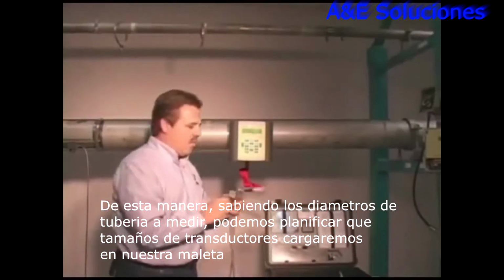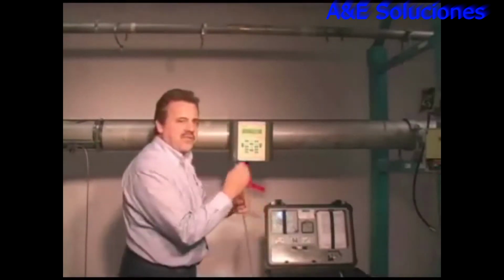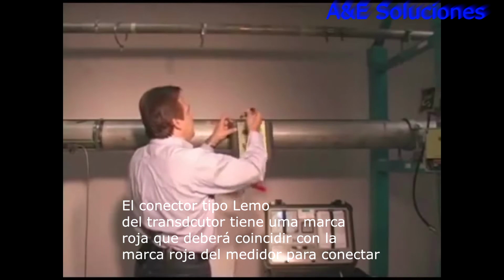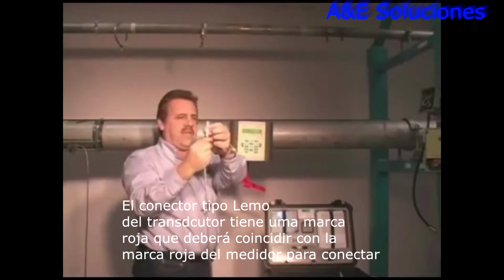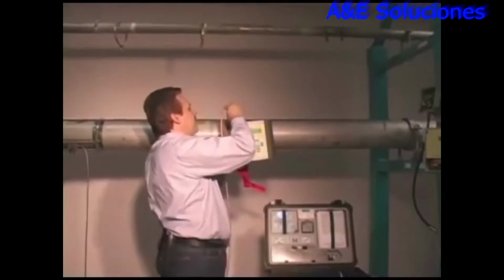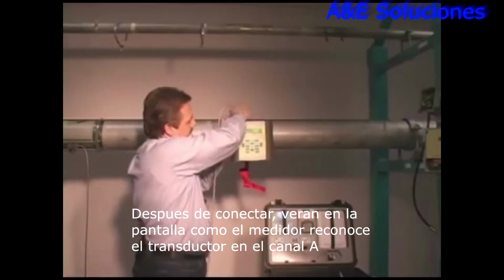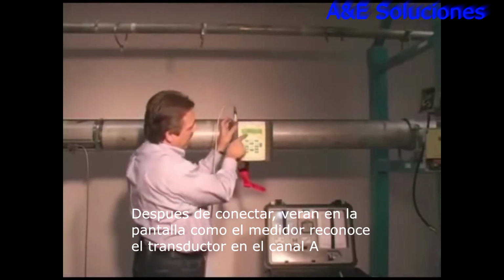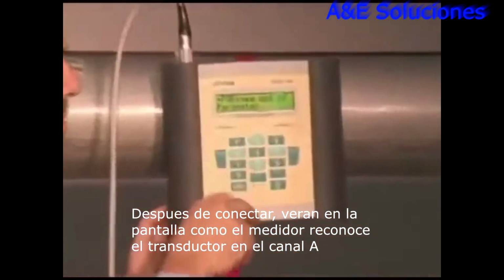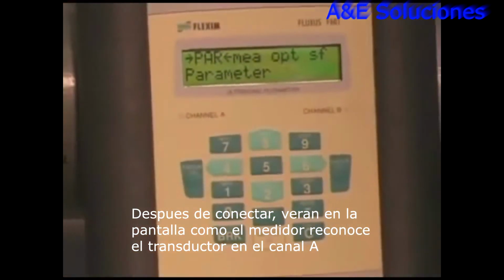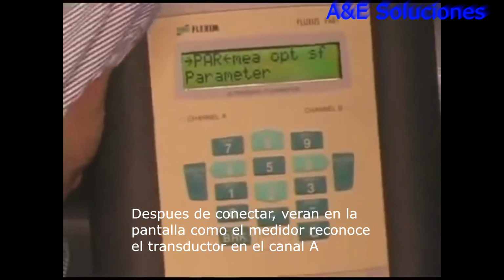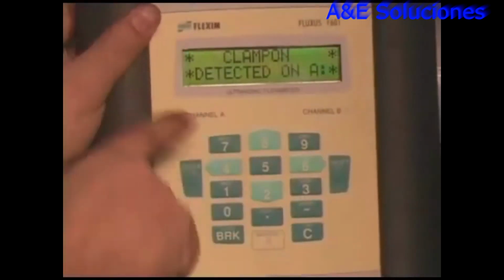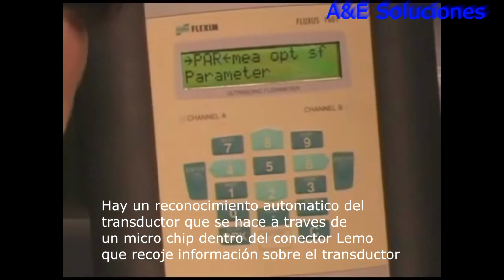So now we're going to plug this transducer in so that the meter has a chance to recognize which transducer we're working with. There's a red dot on this LEMO connector here, and on the top of the connector you'll see a red dot as well. We line up these 2 dots and plug it in. I don't know if you were able to see that if the camera was zoomed in, but when we plugged it in, it said detected transducer on channel A. I'll do that again. Okay, and you see it says clamp on detected on channel A. So it has an automatic recognition of the transducer.